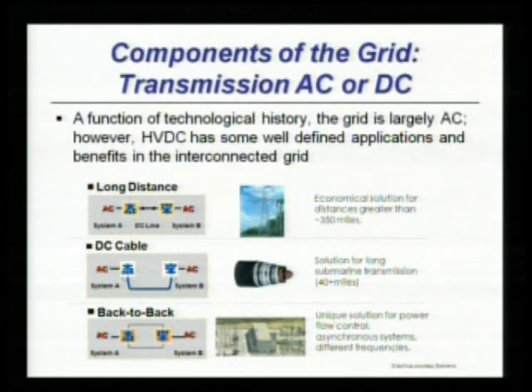The grid has evolved primarily as an AC grid as a function of technological history, but there are places and times where high voltage direct current makes a lot of sense. HVDC is not a new technology—it's been around since the 1950s, and in this country since the late 60s through early 70s. Anytime you start exceeding a distance of about 300 to 350 miles on a transmission line, it starts to make sense to look at high voltage direct current as the appropriate technology for moving large amounts of power.